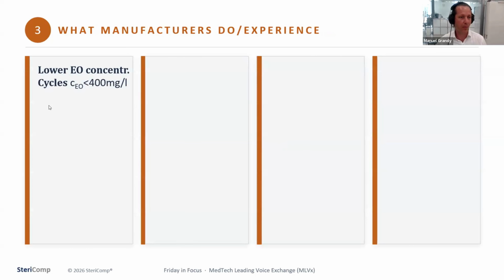One reaction is lower EO concentration cycles, let's say lower than 400 milligrams per liter is usually what you'll see. I think this came from an EPA requirement, an earlier model, saying you must go under 400 milligrams, if I remember correctly. This has now been picked up by sterilization service providers in the US, but also worldwide, and big, mainly US companies, are saying they want cycles lower than 400 milligrams per liter.